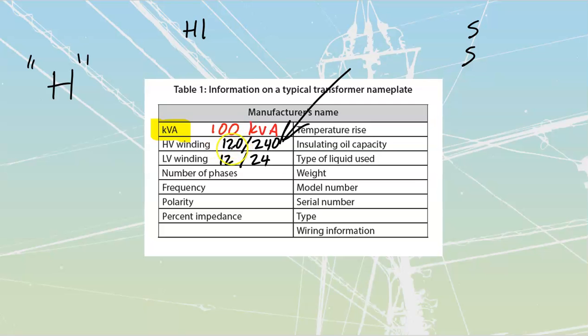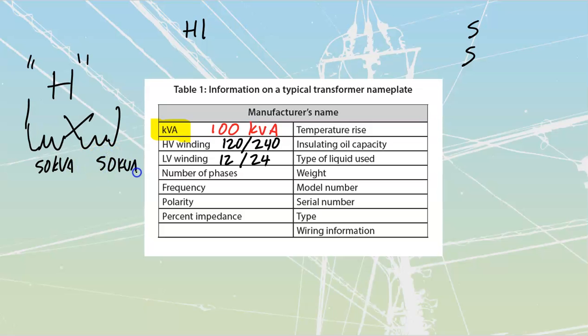The very first one, the first voltage rating that I'm going to have on there, stands for first. Another word for first is premier. So the premier or the parallel connection that we're going to have. Use the S's just to remember that the second is always the series connection for these. If we do have something like this, if that has a split winding here again, I shouldn't have erased that one before, but that split winding, we said before we'd have the total kVA, we'd split it in half, so each side would be 50 kVA and 50 kVA. But then we can also take a look at the voltages. The lower value of voltage is always going to be the individual sections.